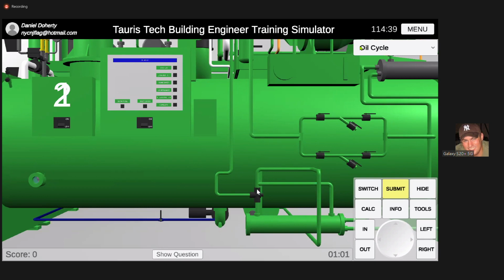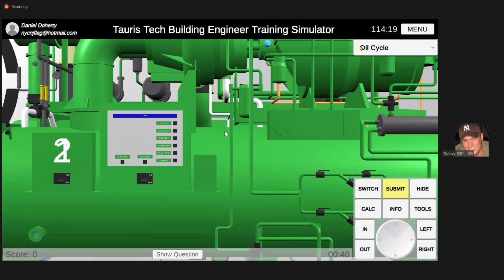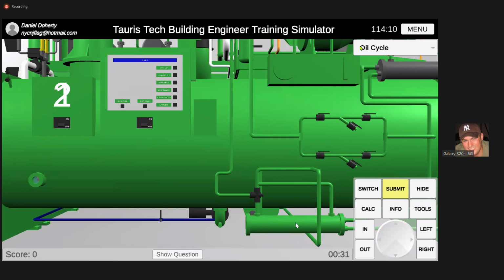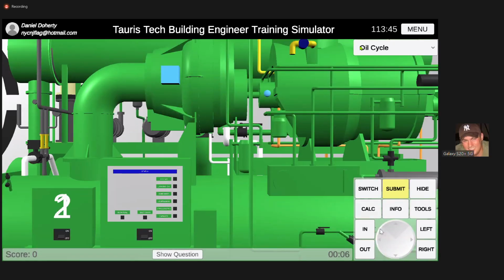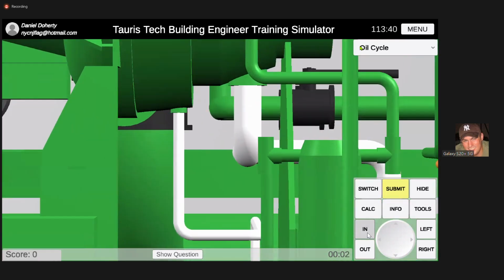So now, if the oil is too hot, this closes on top, and the oil goes this way, and it goes through the heat exchanger, and it comes out on this side, and then that supplies your compressor. This actually goes to your compressor oil filter on top. You see the oil filter, how it goes right into there? Yep. Okay? But at the same time, with this thermal switch, if the oil came back and the oil, let's say, wasn't too hot, it was perfect to go through the compressor, this would open and this side would shut. And now your oil is just going to come in this way, go through the thermal valve, and then go right up to your filter. This filter actually has 2 isolation valves on it. If you look close, you'll see it.